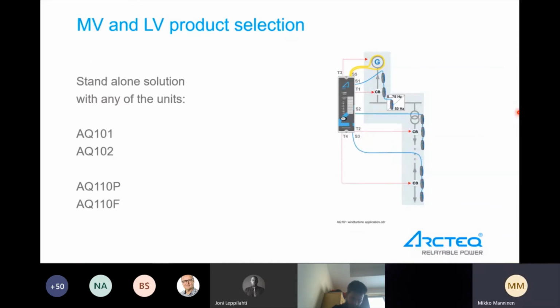Some application examples, for example, with every unit, there is a possibility to make a standalone solution. If current is not necessary, then, for example, here is the light-only wind turbine application. So in this case, the settings would be very easy. There is 1 fiber, and then there are 9 sensors in 3 channels, and 4 trip outputs. And doing the commissioning for such a thing would not take that long. Correct dip switch settings, and then push the button for 3-4 seconds, and then it's done.